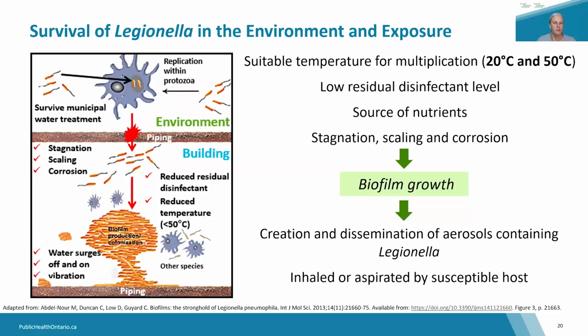temperature and disinfection. So a water system or source that's been contaminated with the Legionella bacteria then needs a means of creating and disseminating aerosols that contain Legionella. They're then inhaled or aspirated by a susceptible host, which then potentially results in illness. So it's not just about the source of the bacteria that's important, but also the conditions that allow it to survive and multiply. If we can remove these conditions, we can help prevent growth.